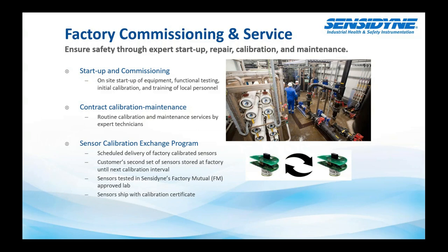We also offer a sensor calibration exchange program, whereas you would purchase two sensors up front. We would store one of the sensors in our controlled environment in the factory. As the preset time comes when you're going to do a calibration swap or sensor exchange, we would calibrate and recondition the sensor and send that to you. You take the sensor, you pull it out of the transmitter that's in the field, you replace it with the new sensor, you put the old sensor back in the box, and you send it back to us. We get it back, we clean it, we recondition it, we calibrate it, and we store it in our walk-in freezer refrigerator, where it does a very good job of prolonging the life of the sensor. So not only is it calibrated to our ISO standards, it's also stored in a controlled environment, which does prolong the life of the sensor.